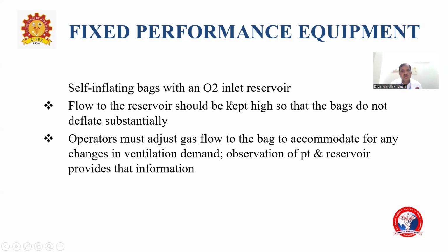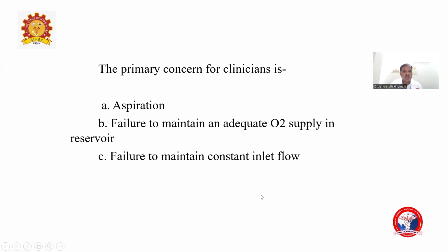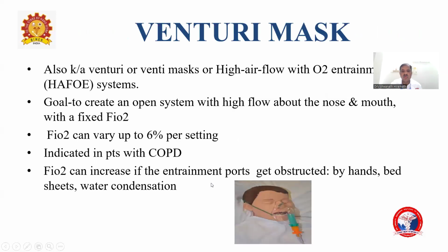Self-inflating bag with oxygen inlet and reservoir. The flow to the reservoir should be kept high so that the bag will not deflate substantially. The operator must adjust the gas flow to the bag to accommodate changes in ventilation demand, observing the patient and the reservoir. Primary concerns are aspiration, failure to maintain adequate oxygen supply in the reservoir, and failure to maintain constant inlet flow.